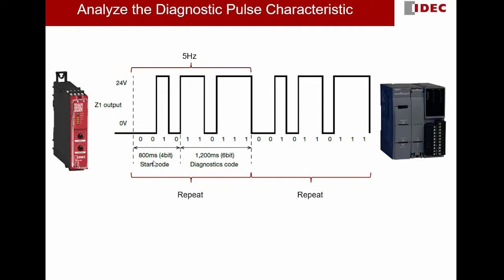If you would like to extract the diagnostic code out of this continuous pulse, there is one very important characteristic we will use in our PLC program: this 6-bit diagnostic code is actually surrounded by two start codes — 0010. So later on in our logic, we will specifically identify this pattern. When we see that within 14 bits the pattern is initiated and ended with 0010, we will take the 6 bits in between.